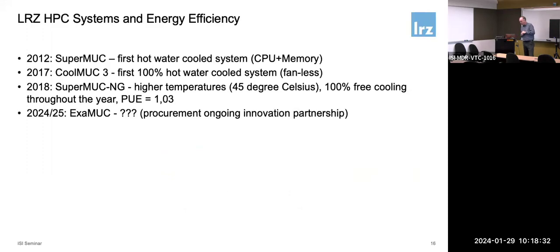What we've been doing is thinking about computational performance and energy together, in terms of energy efficiency, and we've tried a couple of things. In 2012 we had the world's first hot water cooled system, where hot water was cooling CPU and memory. Hot water means the inlet temperature is high enough that we can use free cooling, so the inlet temperature must be higher than what is outside. We go in with an inlet temperature of 45 degrees Celsius, around 110 Fahrenheit, and come out with hotter water, which we then cool back down to the inlet temperature using only outside air. So we don't need any extra energy for cooling the system, we just make sure the system can live with hotter temperatures.